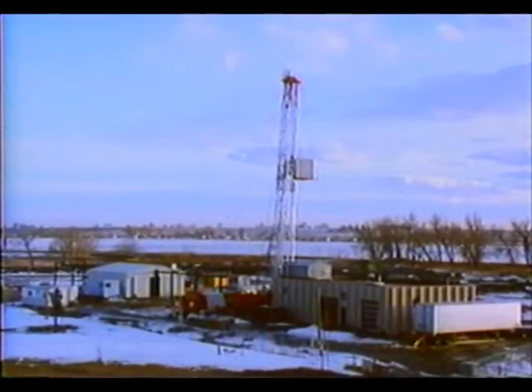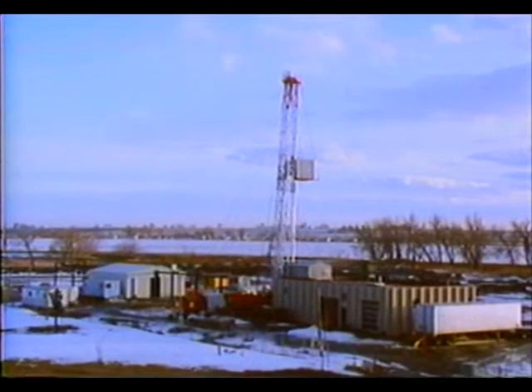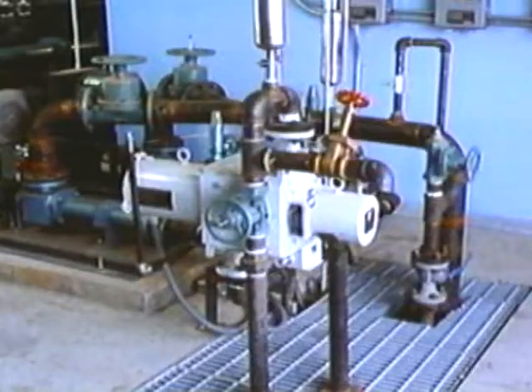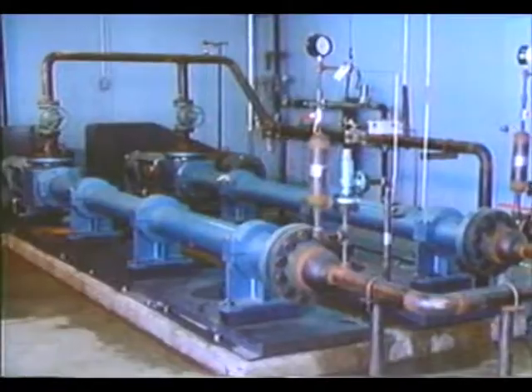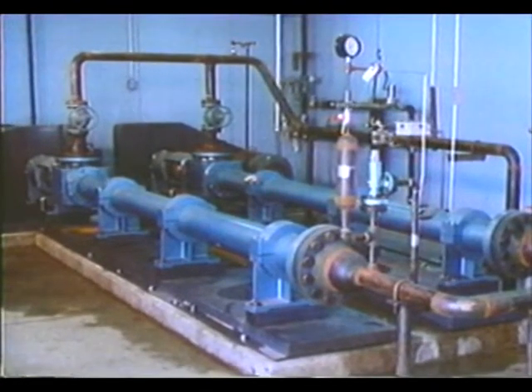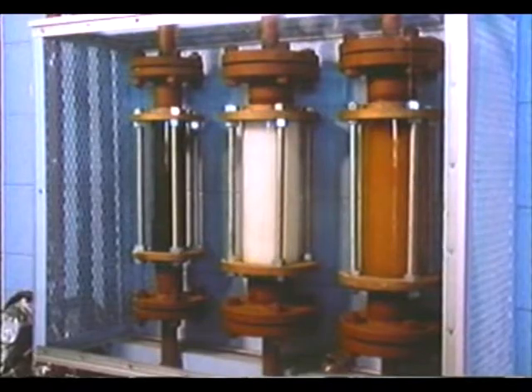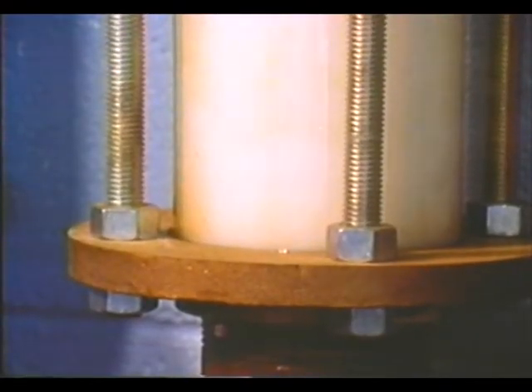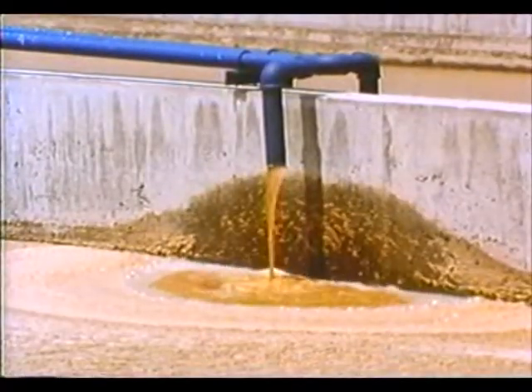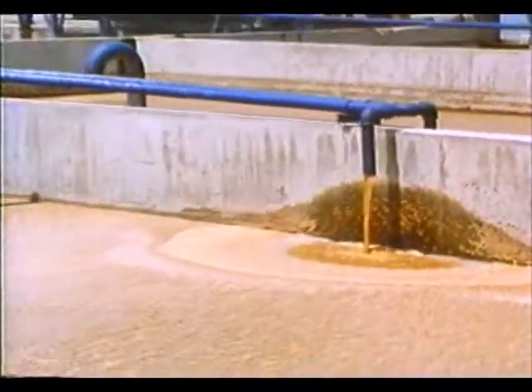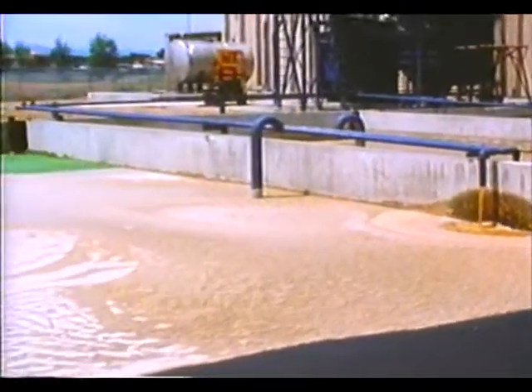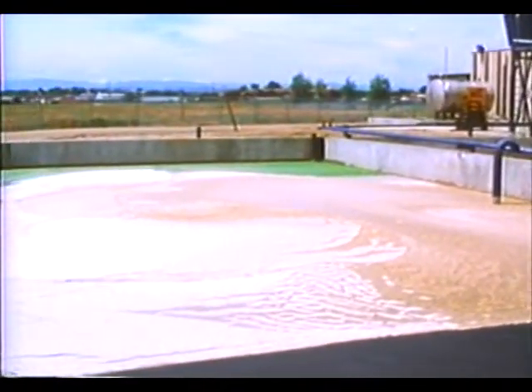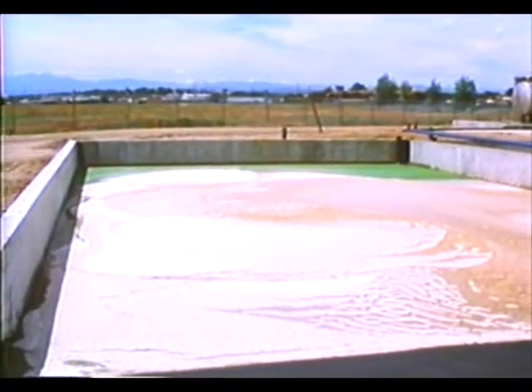The vertical tube reactor is an innovative, cost-effective, and controllable method of solving difficult sludge processing and disposal problems. The vertical tube reactor is a below-ground system that uses wet oxidation to convert various wastewaters and sludges to water, carbon dioxide, and a small amount of inert and sterile ash. Since wet oxidation is a chemical rather than a biological process, it is not affected to the same degree by variations of strength and flow of waste.